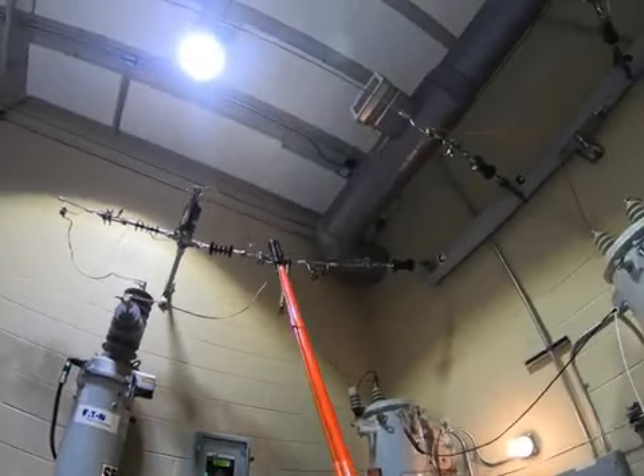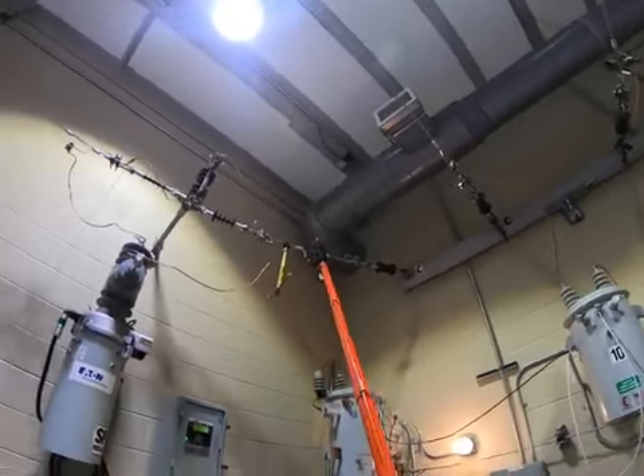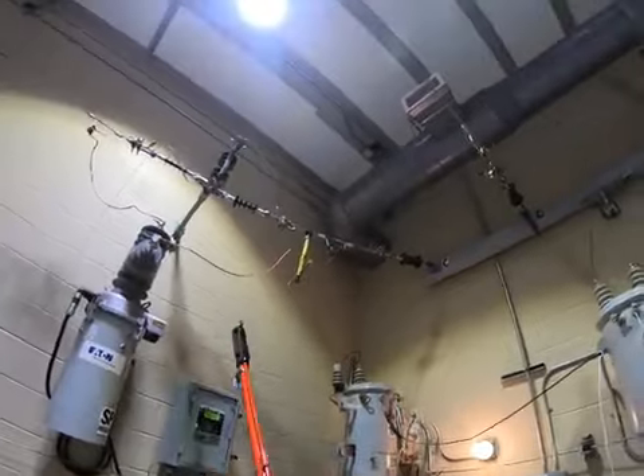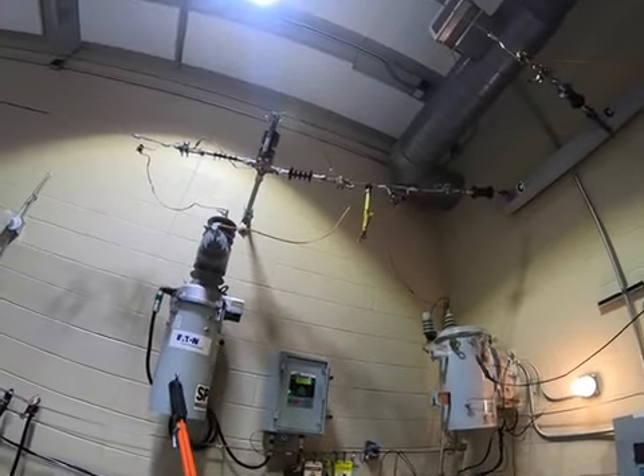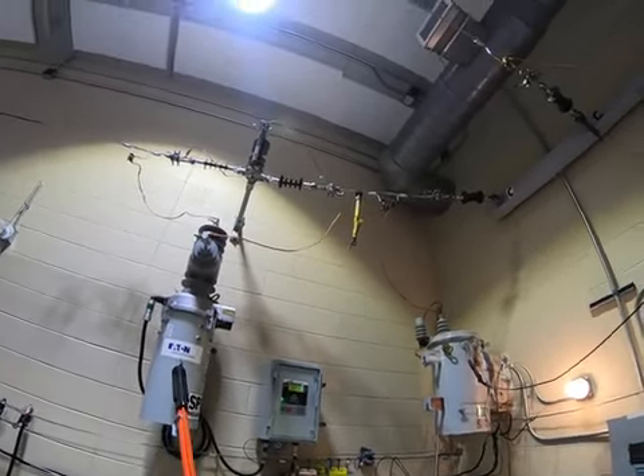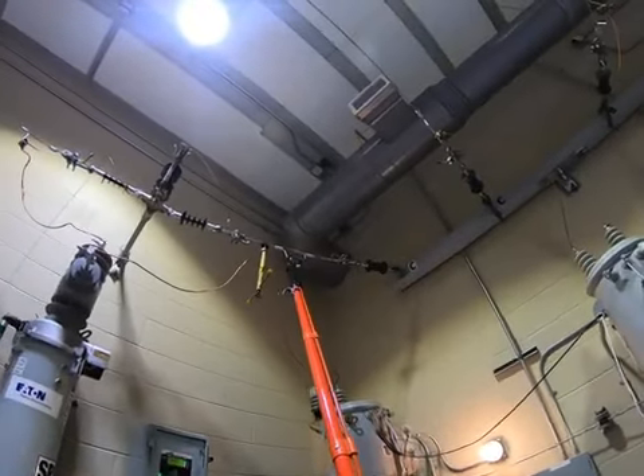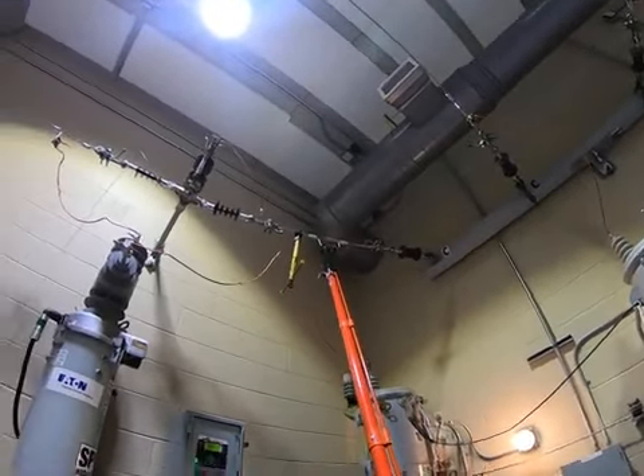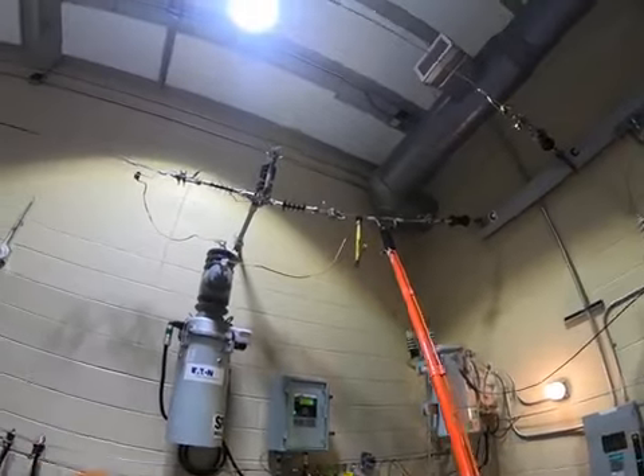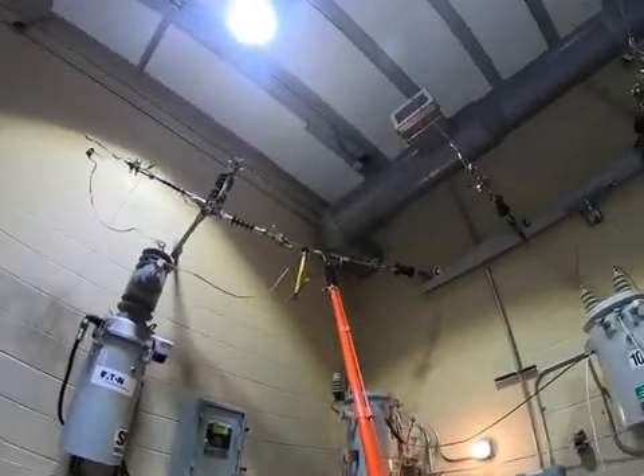We have to make sure as we take these off, we don't let the first jumper drop and touch the tank or anything grounded, just in case these contacts in here lied to us and weren't actually open. As I take this one off, if the contacts stayed closed for whatever reason and let this jumper drop, we'd obviously have a fire right here, phase to ground fault.